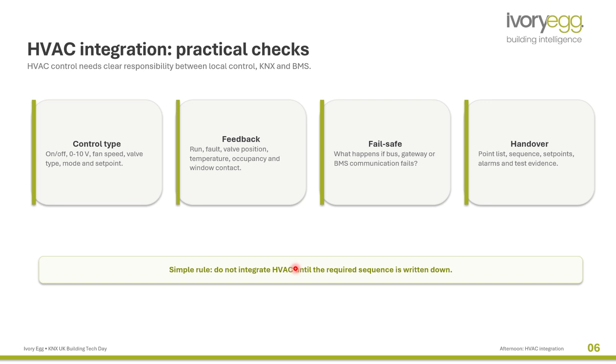So point list, sequence, set point, alarm, and test evidence. Simple rule: do not integrate HVAC until the required sequence is written down. Yes, this point is going to be considered in the plant room.